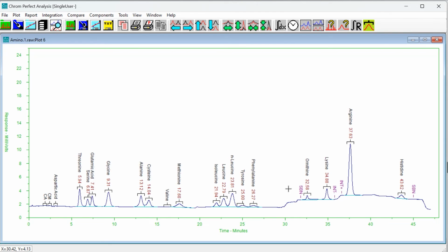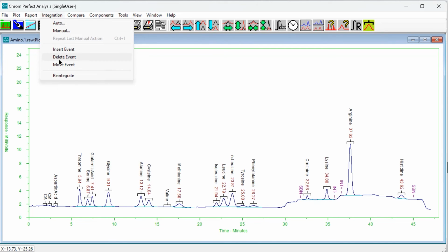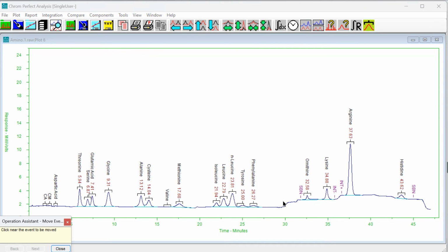But has it? We have irreversibly changed the results of all older files that use this method. If there has been any retention time shifts from run to run, our new event might cause incorrect results due to a badly drawn baseline. Additionally, all future files that we acquire using our new amino method will now show the same timed event at the same spot in the run.